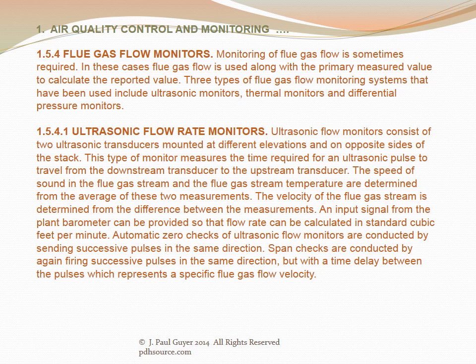Ultrasonic flow monitors consist of two ultrasonic transducers mounted at different elevations and on opposite sides of the stack. This type of monitor measures the time required for an ultrasonic pulse to travel from the downstream transducer to the upstream transducer. The speed of sound in the flue gas stream and the stream temperature are determined from the average of these two measurements, and the velocity is determined from the difference. An input signal from the plant barometer can be provided so that flue flow rate can be calculated in standard cubic feet per minute. Automatic zero checks are conducted by sending successive pulses in the same direction; span checks are conducted similarly but with a time delay representing a specific flue gas flow velocity.